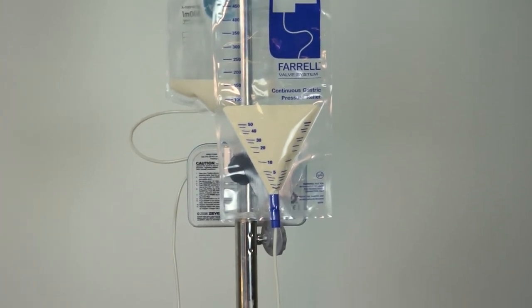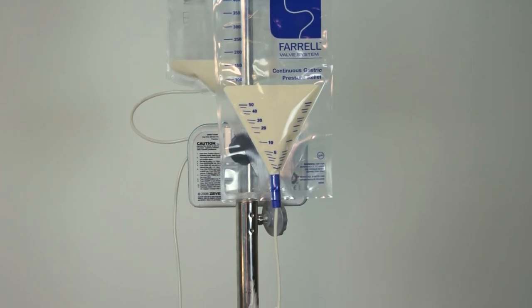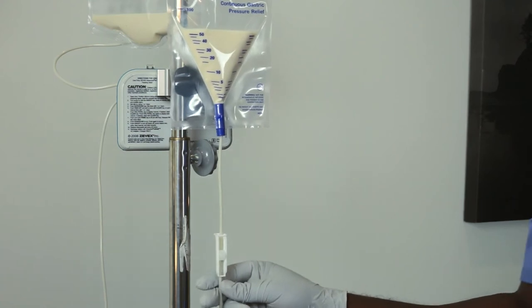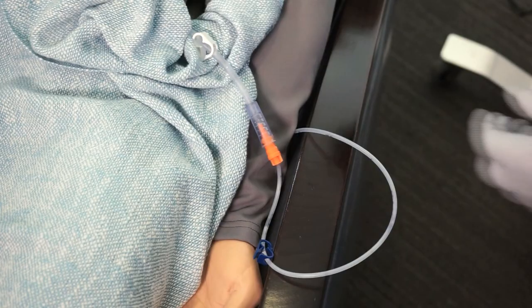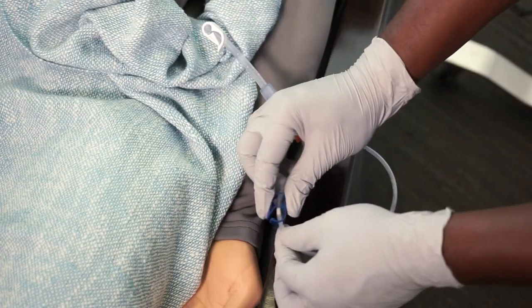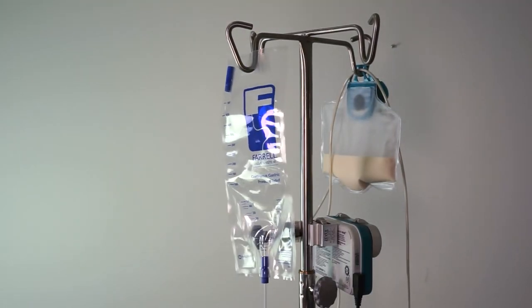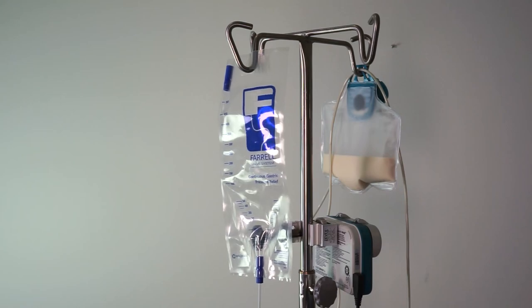If a large volume of fluid is in the Farrell tubing after resolving an occlusion, adjust the white roller clamp of the Farrell bag to prevent a free flow bolus of fluid into the patient. To discontinue Farrell valve operation, close both the white and blue clamps on the Farrell line. Change the Farrell bag when the feed bag is changed. The maximum recommended use of the Farrell bag is 24 hours.